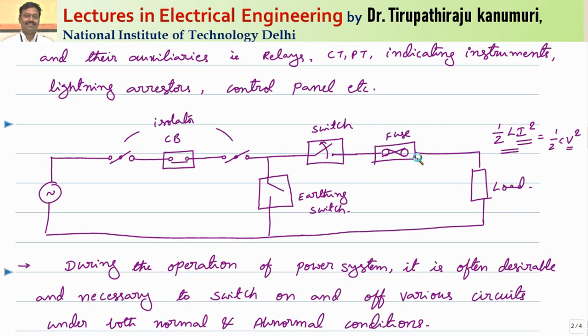The disadvantage of using a fuse is that whenever the fuse is blown, due to some problem, you have to replace the fuse element, which takes some time. As you go for higher-rating equipment — for example, in a transmission line where continuity of supply is a major concern — that fuse replacement takes time, and many times that much time is not permitted. The second disadvantage is that sometimes during transient conditions your fuse may also operate. For high-capacity power transmission like transmission lines where continuity of power is critical, that cannot be tolerated. That is why a switch or fuse is used only for low-voltage, low-current applications.